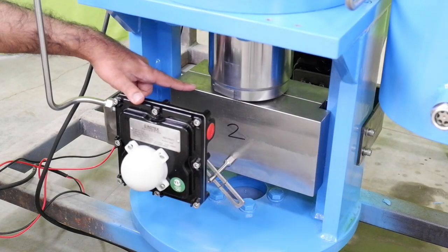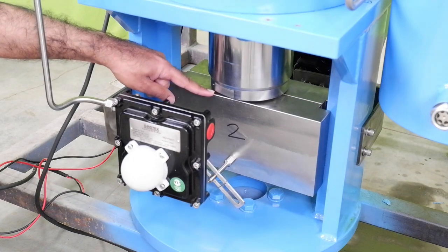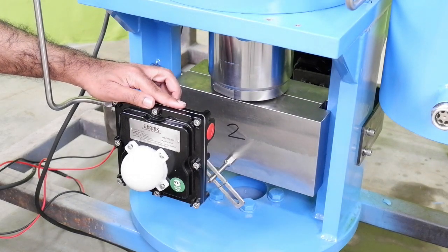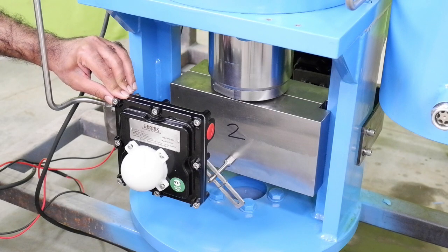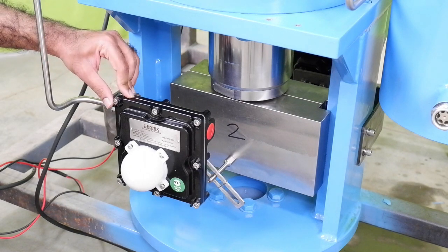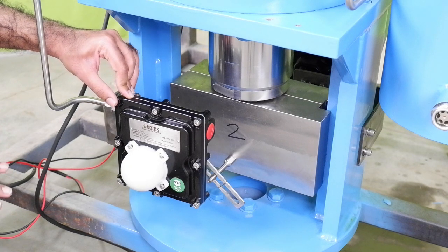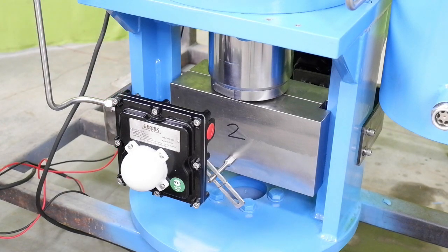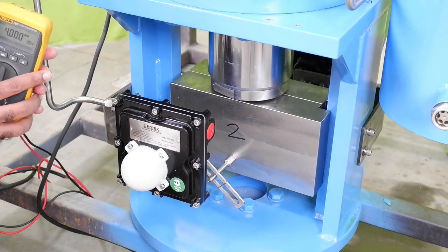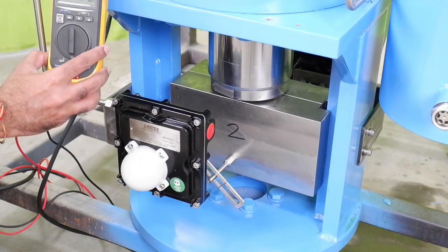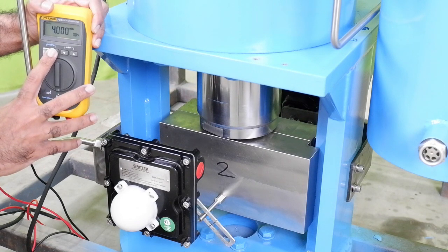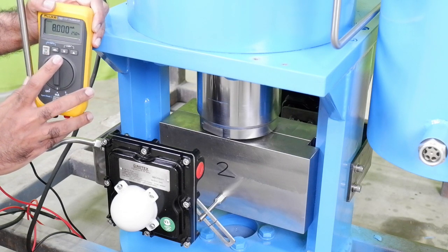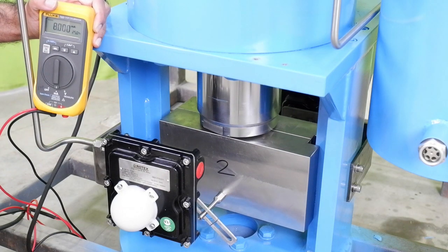Here the cylinder is connected to a split coupler. The split coupler reduces the play between the stem of the globe valve and the cylinder. The transmitter is connected directly to the coupler along with the linkage, which improves the accuracy of the system. Now we will see how the cylinder opens and closes with respect to the set point signal. Here the cylinder is in closed condition. So now we will open it by changing the set point. You will have to change it to remote mode.